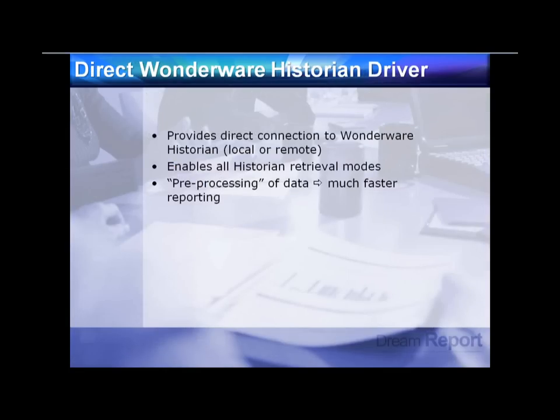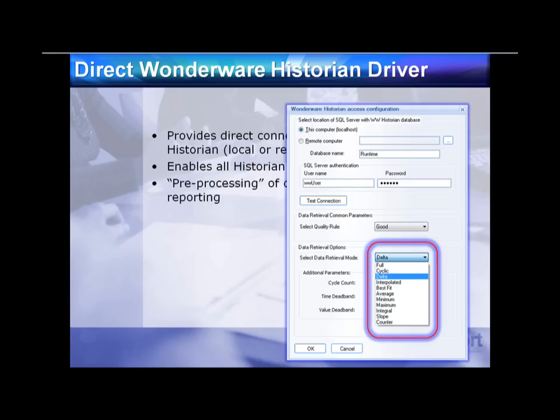The Direct Wonderware Historian driver provides native connection into Wonderware Historian, locally or on any remote machine, exposing all of Historian's retrieval modes to take full advantage of its fast data retrieval. For example, if you need hourly integrals on a flow meter, using the integral retrieval mode from Historian at one-hour intervals allows you to extract large amounts of data very quickly. You simply configure where the Historian resides, test your connection, then choose your retrieval mode and any associated parameters.